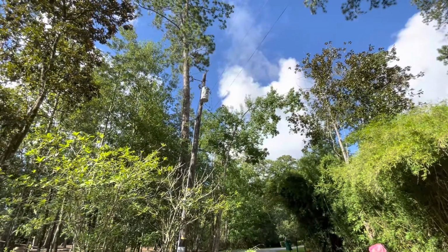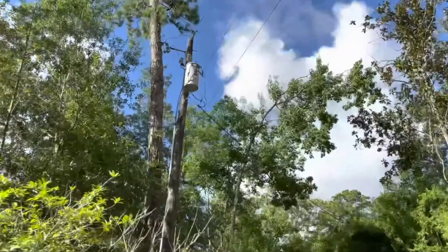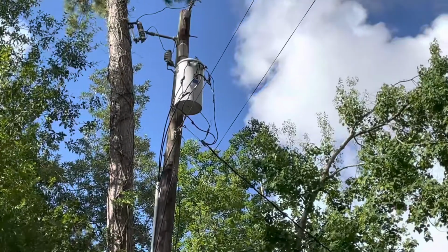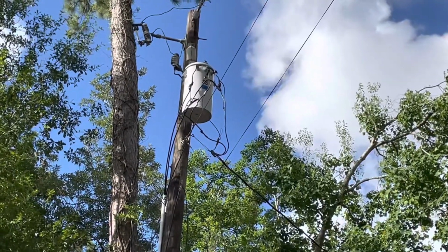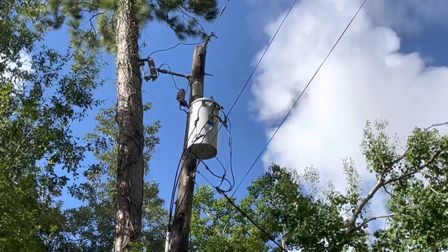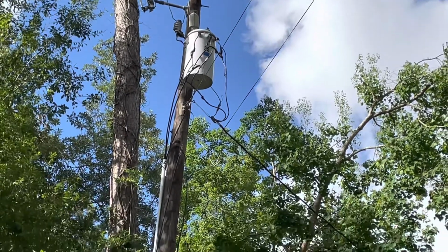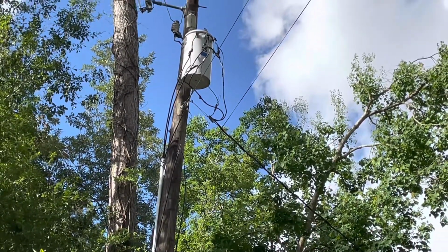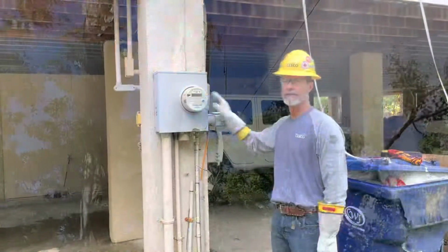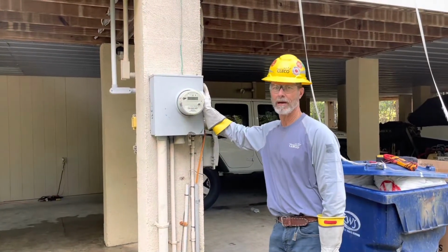We're looking at a single pot, single phase 25 kVA transformer. The service voltage for this transformer is 120 phase to ground, 240 phase to phase. It has an overhead service and an underground service. This is a single phase 3-wire customer.